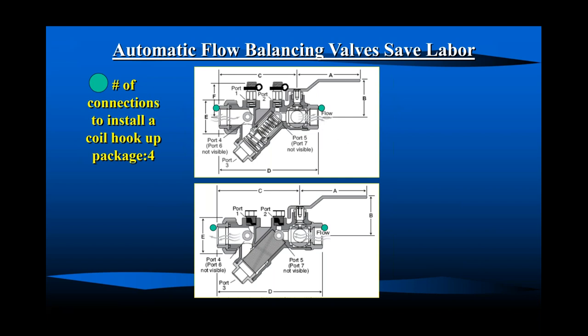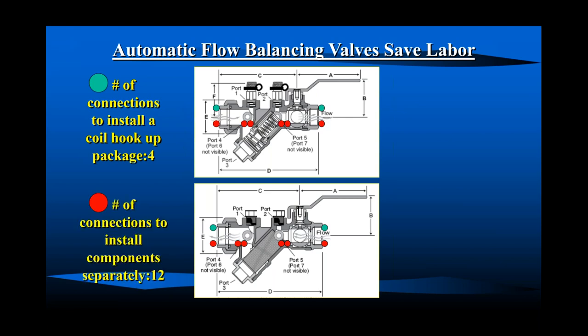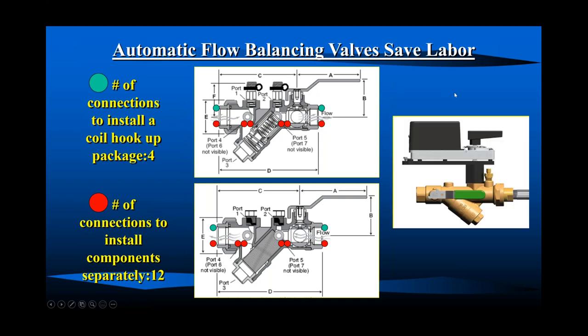If this was all installed separately in the field, 12 connections. Labor being what it is in New York City, not a bad way to go. And again, all things being considered, if you can combine more things into one valve body, this is an automatic flow balancing valve, modulating valve, on-off valve.